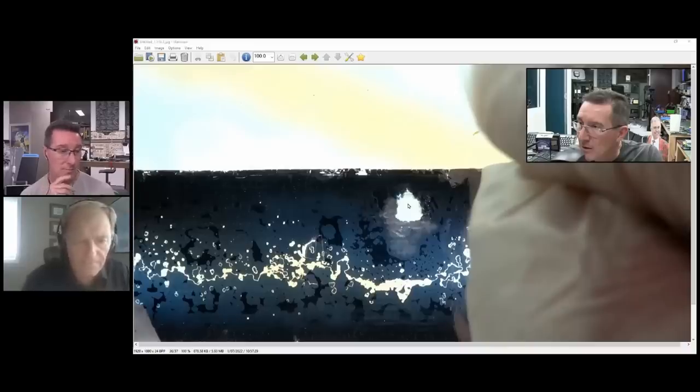But right, what we're seeing here is in the crack lines, the lightning bolt looking thing. That almost went through the whole thing. You have this reaction of the moisture, and what's occurring is that you're getting a moisture effect that's actually causing the electrodes to change. They're getting more resistive. They're getting some migration or movement, oxidations, changing resistances. So those voids are most likely, to some extent, like a micro healing or an impulse degradation. That's how I'd explain that lighter center section.